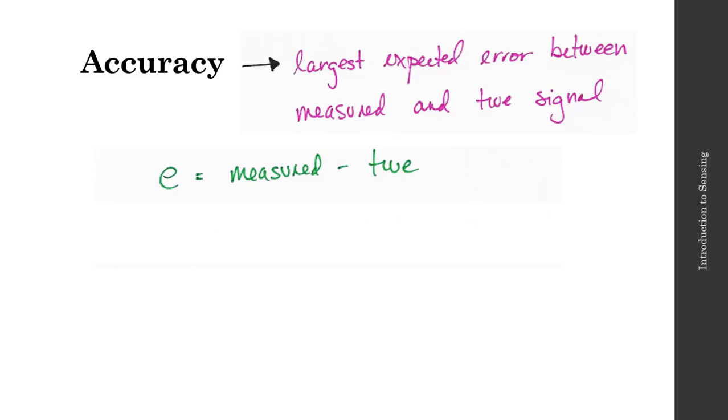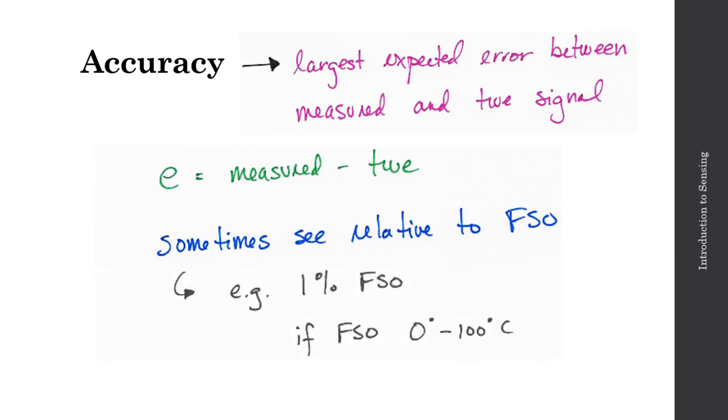On a data sheet, you might see the accuracy relative to the full-scale operating range, relative to the FSO. So, for example, let's say you saw that the accuracy on the data sheet was defined as 1% FSO. And if you knew from elsewhere on that same data sheet that the FSO was 0 to 100 degrees C, let's say this is a temperature sensor, then I would expect my accuracy, or that largest expected error, to be plus or minus 1 degrees C.